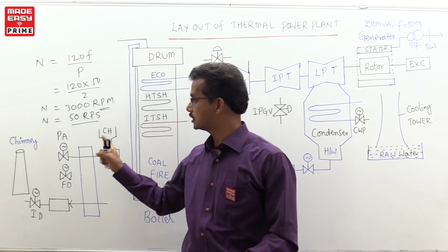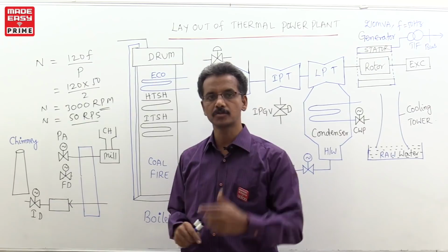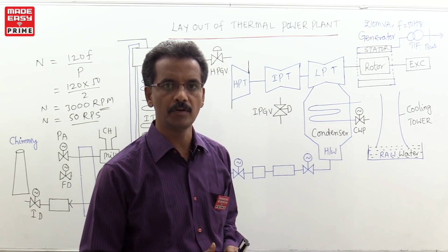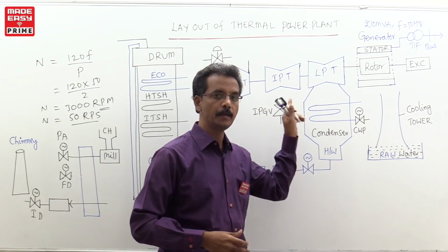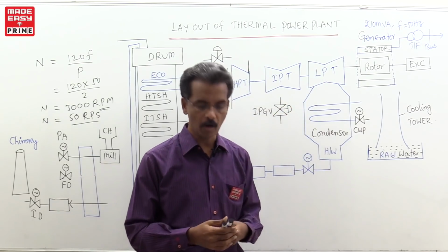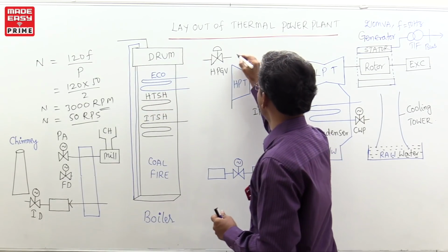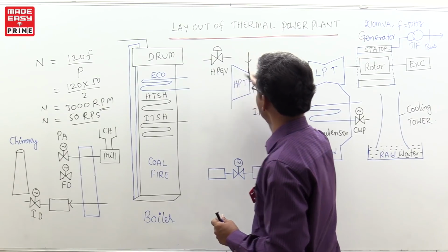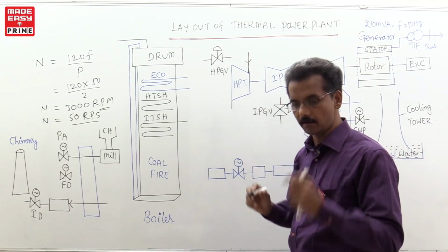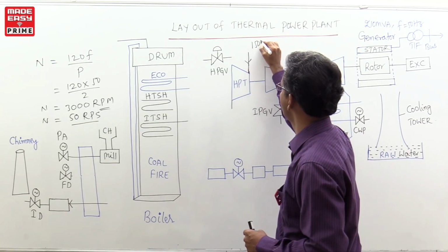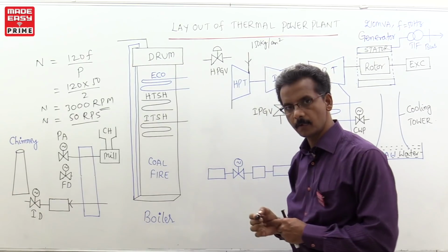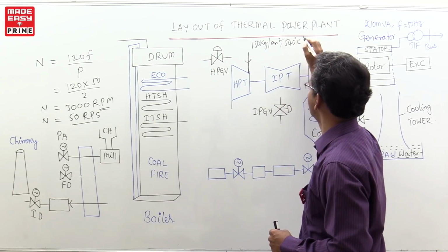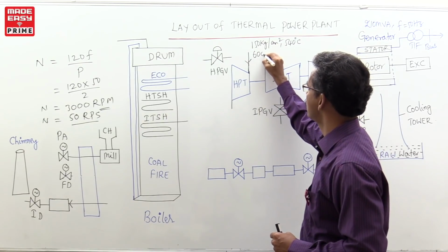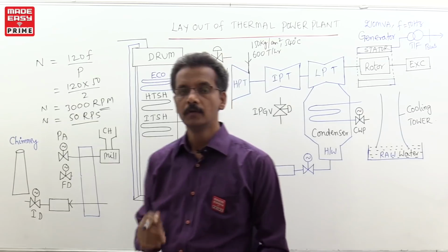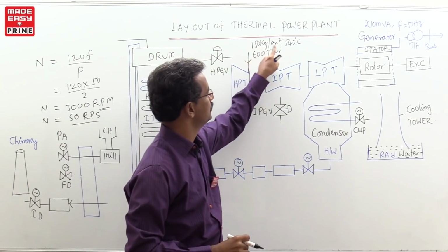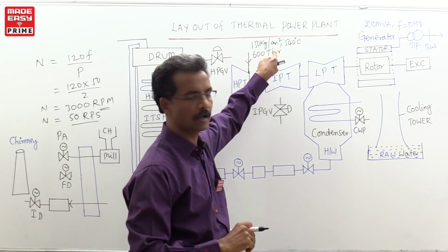At a speed of 50 revolutions per second, within a second it has to make 50 revolutions. For producing this, we have to admit steam into the turbine in a very high quantity. So these are the practical values of the parameters of the steam we admit into the turbine: 150 kgs per centimeter square of steam pressure, 540 degrees centigrade of steam temperature, and 600 tons per hour of steam flow rate that we have to send inside the turbine.